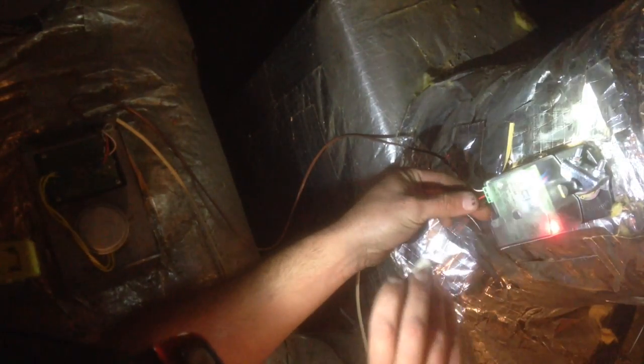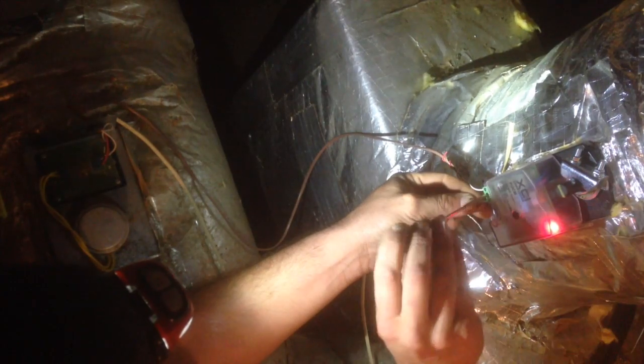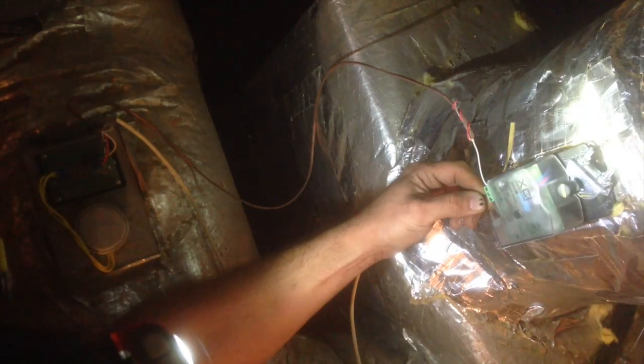Now, when the red light is on, it means that it is closed completely. And then if you see a green light below it, it is fully open. Now, what we could do, just to test it now, is take the power closed wire and the power open wire and switch them.